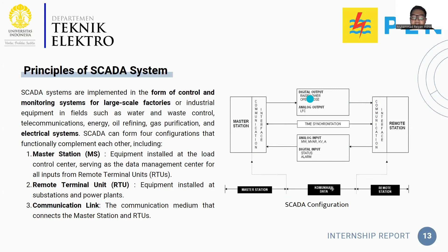The third part is the fundamental theory: the principles of the SCADA system, which consist of three parts - the master station, which is equipment installed in the load control center; the remote station, equipment installed in substations and power plants; and the communication link, the interconnection between them.